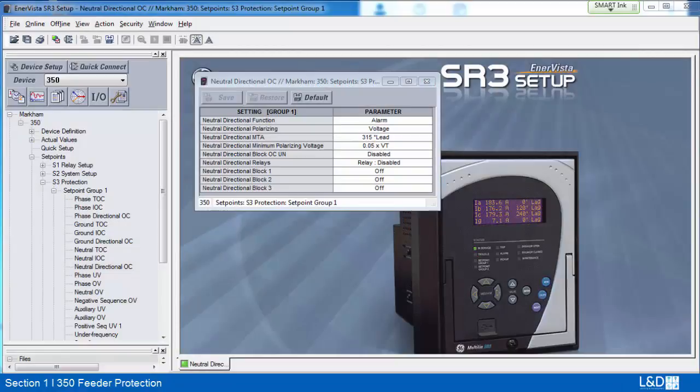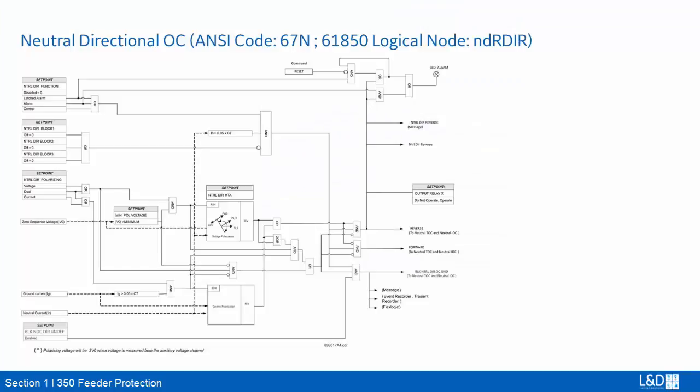From the logic diagram, when polarizing is set to voltage, the direction is determined by comparing the angle between the operating neutral current and the voltage against the set MTA angle. If voltage drops below the minimum polarizing voltage setting, the neutral directional element is undefined. When current polarizing is selected, the direction of the neutral current is determined with reference to the measured ground current. The fault is detected in the forward direction when ground current is within 90 degrees of the polarizing current; otherwise, it is detected as reverse. The neutral directional element is undefined if the polarizing ground current drops below 5% of the ground CT.